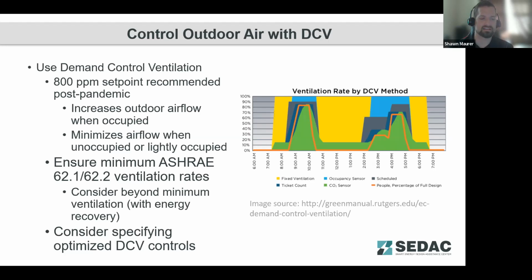Something else to consider is optimizing your DCV controls. There's different ways to do DCV control that are more beneficial for different space types than others. You can do CO2 control in spaces that have irregular occupancy patterns. Private offices, classrooms are kind of decent examples. Timed ventilation rates are kind of better for spaces that have regular occupancy patterns. Occupancy sensing type controls are better for spaces that have widely varying time of use, but relatively consistent occupancy numbers.